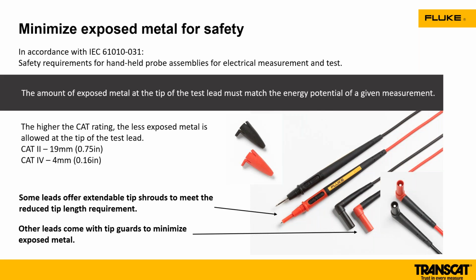The longer the metal, the lower the category rating. As you can see here, that 19 millimeter goes to that category 2 environment, whereas with the smallest amount of metal exposed, we can keep that category 4. So it's really critical. Don't throw those caps away. If you're working in higher category environments, we want to make sure that less exposed metal is critical.